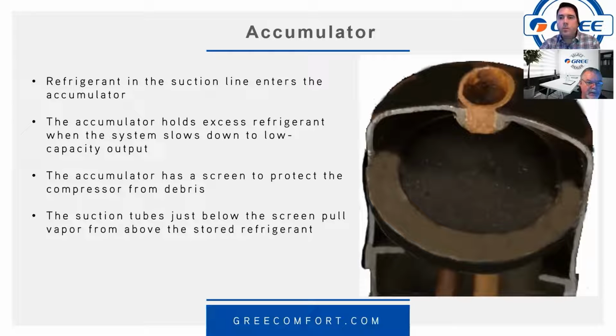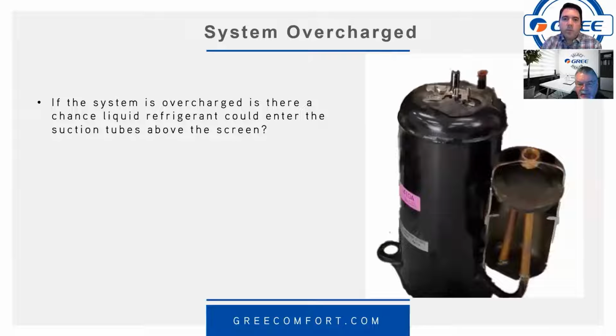Refrigerant on the suction line enters the accumulator. The accumulator holds the excess refrigerant when the system slows down to low capacity. And they do have a screen in there to help protect it from some debris. And then the suction tubes just below the screen pull vapor from up here, and then the liquid stays down below. So like little snorkels, right? Refrigerant will be in the lower part here. Suction always enters through here, so you've got a little bit of protection.